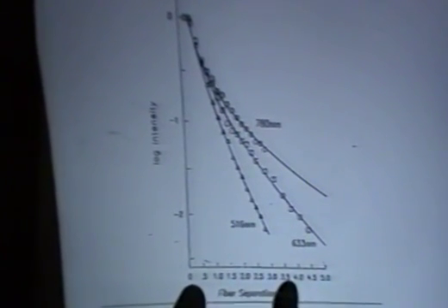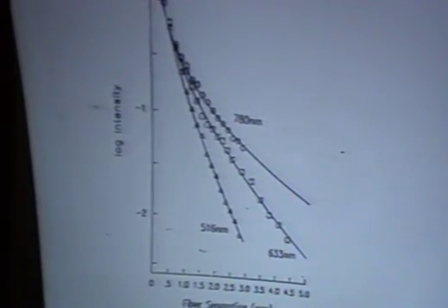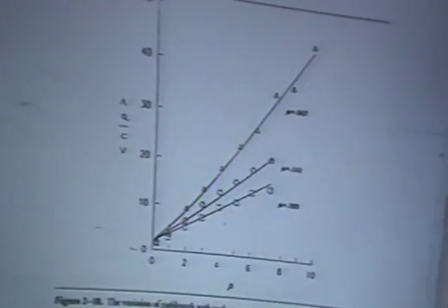To talk briefly about the measurement volume, if you look at the intensity of the reflected light off of tissue as you vary the fiber separation, this is from skin, there's a very strong falloff. This is log 10. So there really is a limitation of how far apart the fibers can be put. As you move the fibers farther and farther apart, the multiple Doppler shifting off of red cells becomes a more extreme problem. It becomes harder to linearize the output. And one can see that as one varies the fiber separation. This is the path length. It increases almost linearly, and it will change with the optical parameters of the tissue.